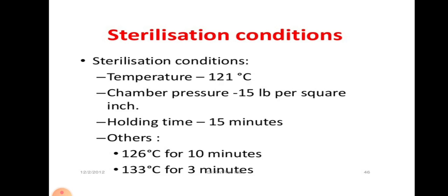Sterilization conditions of an autoclave: the temperature is above 100 degrees centigrade, that is 121 degrees centigrade, which is obtained when 15 LBS pressure per square inch is applied. This is held for 15 minutes to destroy all vegetative cells and spores of bacteria and viruses. The timing can be reduced to 10 minutes where the temperature is maintained at 126 degrees centigrade, and at 133 degrees centigrade the holding time is 3 minutes.